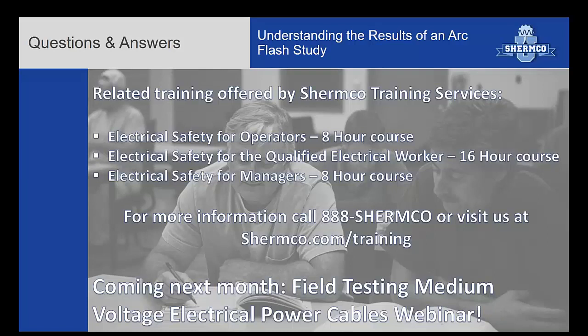Definitely feeder lengths, when you're feeding one sub to another. We probably normally don't do arc flash at the motors because typically those are de-energized. It's not labeled. But definitely when you have one feeder from one sub to another, all those cable lengths play a big role in what is the actual arc flash at that area. Okay. So we'll follow up and we'll get to where the plus or minus 20 comes from.